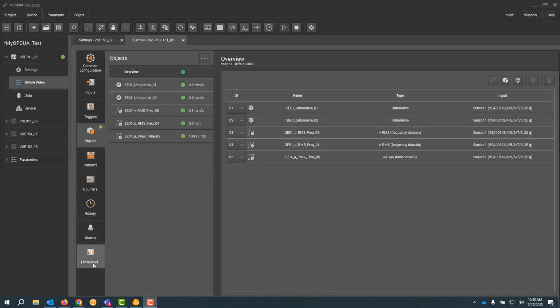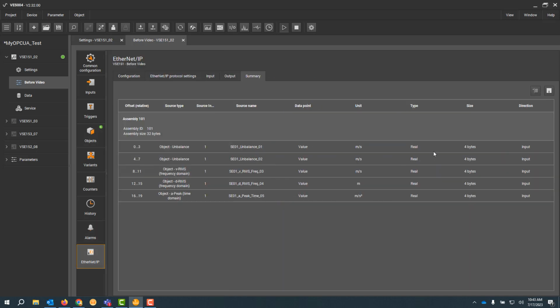As an example, real quick, I'll go to this Ethernet IP VSE, and just as a correlation to what would be going on would be that the data here in the assembly is 1, 2, 3, 4, 5 real values, and this is how the data is being sent over to Moneo, for example. If suddenly we remove, say, object 4 here, in the data, object 5 actually shifts up. And then the data that you have feeding into Moneo once you make and write a change like that to the VSE is not correct. It's not looking at the right data set.